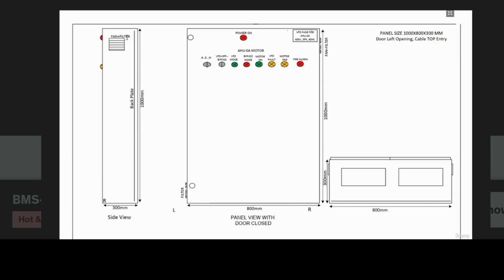Then here we have a filter for proper ventilation inside this MCC panel, because there is a VFD inside this, and due to which heat will be generated inside the MCC panel. So it is necessary to have forced ventilation. If you are in the operation and maintenance team, you shall properly clean this filter and ensure that the fan is running properly to avoid failure of the VFD components.